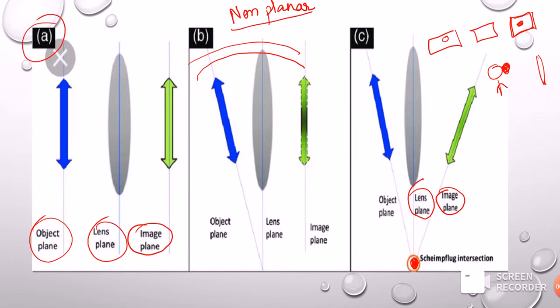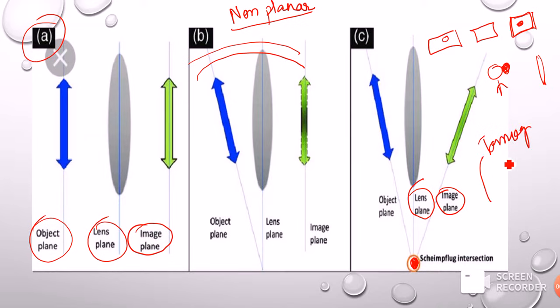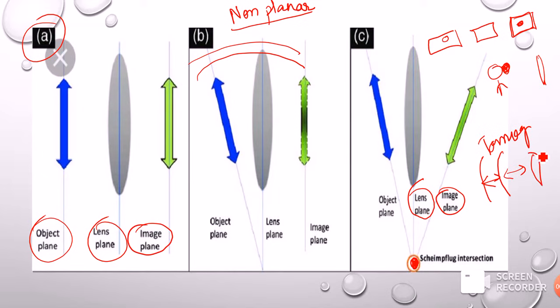The Scheimpflug technology takes cross-sections throughout the cornea by tilting the lens plane and bringing all three planes to a single focus, producing a tomogram. This provides the anterior surface, the posterior surface, and the thickness of the cornea. Additionally, the anterior chamber depth and details of the lens can sometimes also be determined.